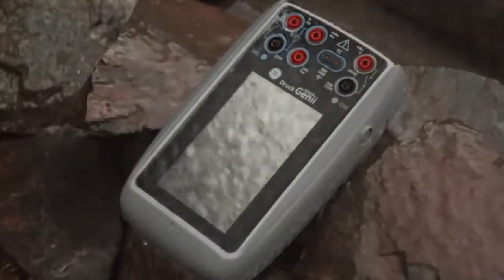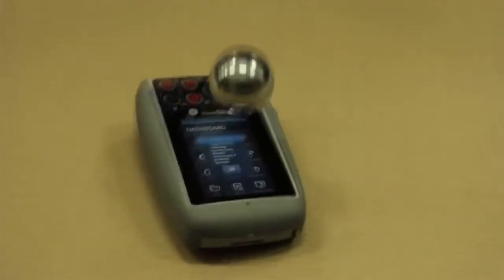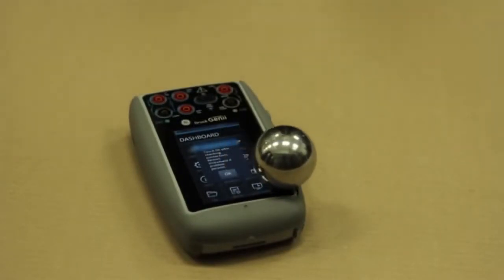A mechanical design goal was to devise a compact enclosure for a multifunction calibrator that was both robust and weatherproof, preferably to IP55. These features provide a rugged, highly effective, multifunctional calibrator for indoor and outdoor use in extreme conditions.